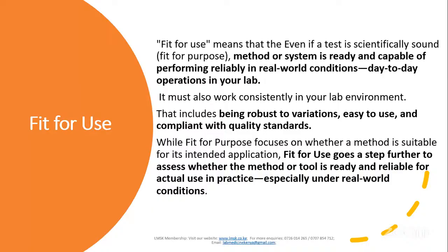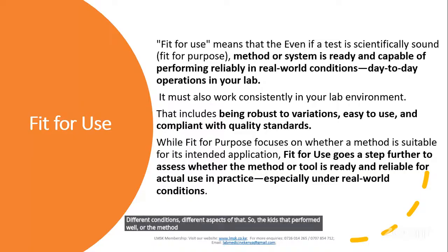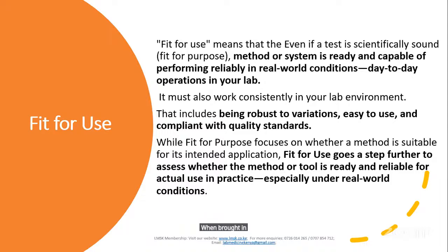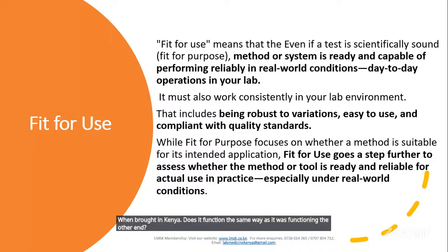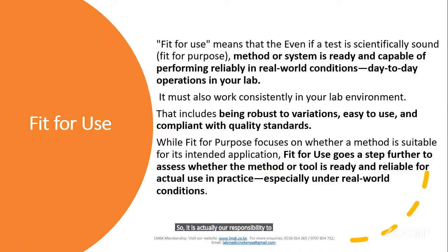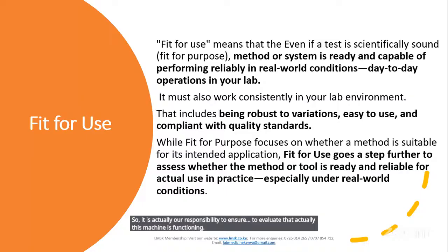A test methodology or test kits were manufactured in Europe. They were deployed for usage in Kenya, in Mombasa. Different conditions, different aspects of that. So the kit that performed well, or the methodology that performed well in Europe, the analyzer that was functioning properly in Europe, when brought to Kenya, does it function the same way as it was functioning the other end? So it is actually our responsibility to evaluate that this machine is functioning effectively the way it was deemed during the laboratory manufacturing of it.